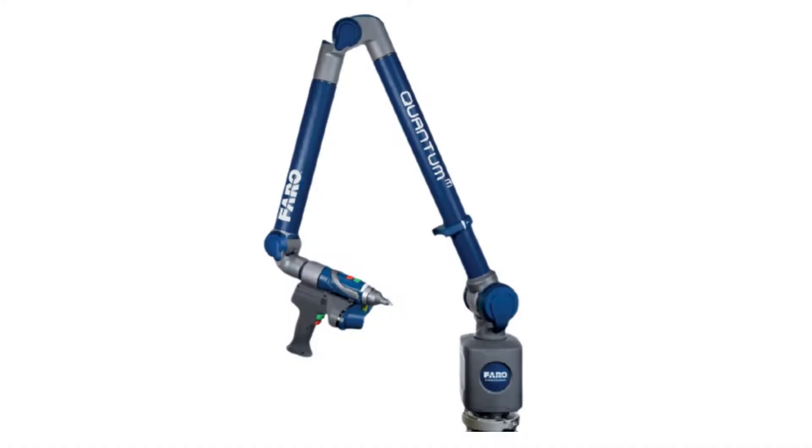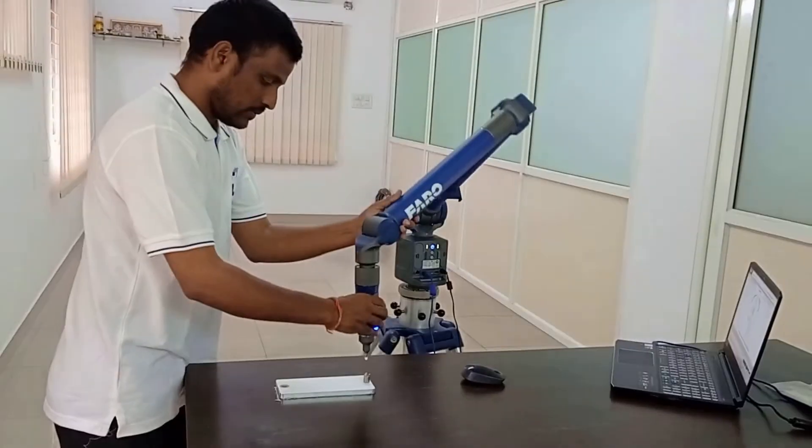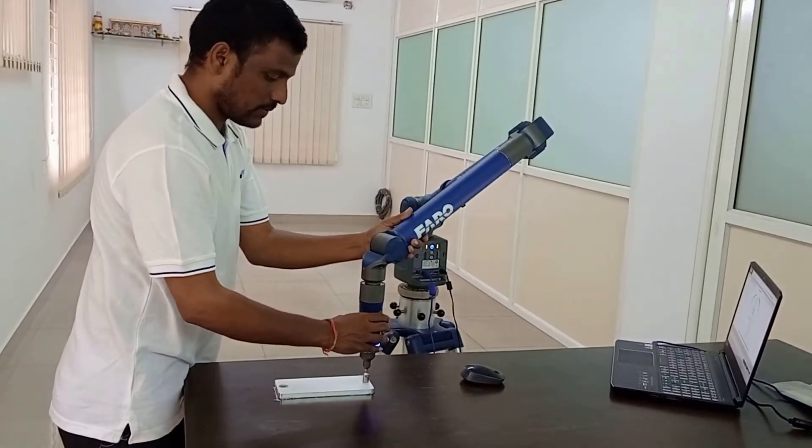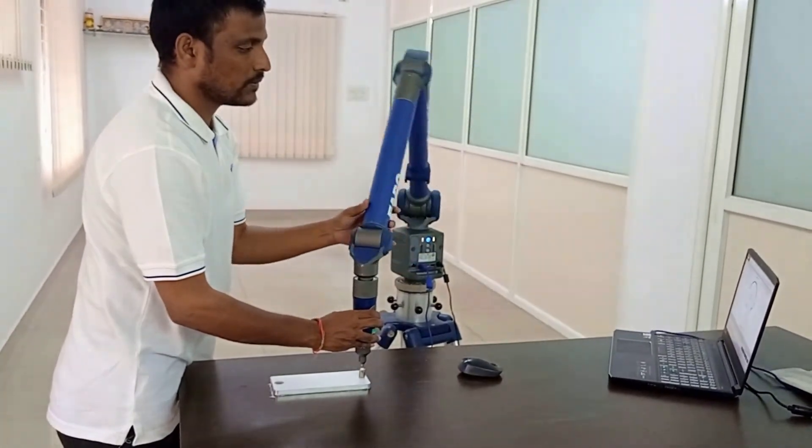Measurement arms are 3D measurement devices like the Faro arm developed in response to growing need for a probing solution that provided more portability and flexibility than a fixed CMM. So that is why probes are connected to the quantum arm and we are going to execute the inspection process.